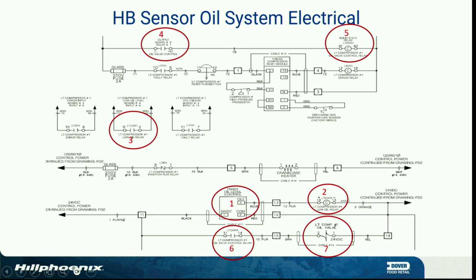Exactly. Then why call me? Guys, I get calls all day. Hey, my compressor tripped, my rack's tripped on oil. Okay, what have you looked at? Well, I don't know. You tell me. Well, first of all, how many CO2 racks have you worked on? You're the apprentice. Well, this is my first one. They told me to come up here and look at it. I said, all right, is the rack down? No. Okay. Reset your compressor. Clear your alarm, reset your compressor. If it comes back on, call your supervisor.